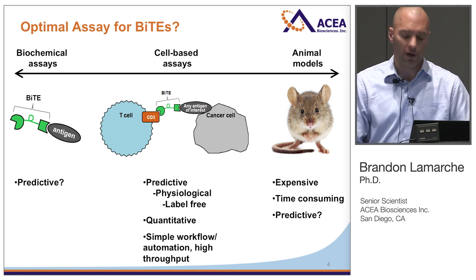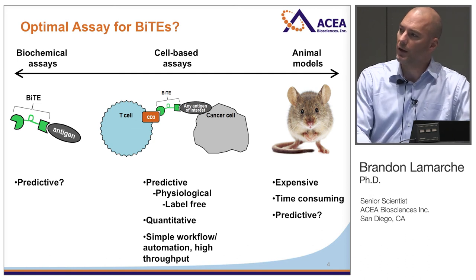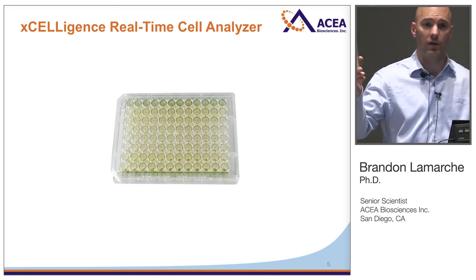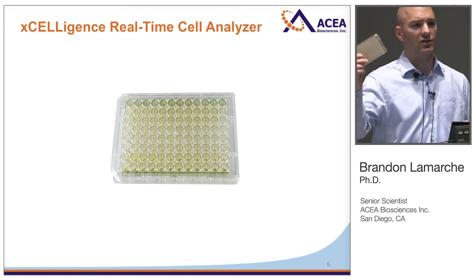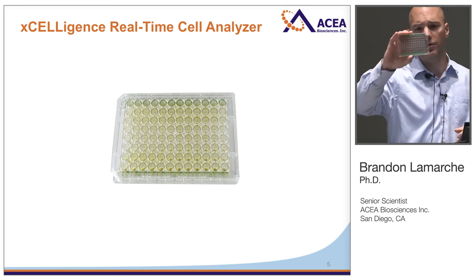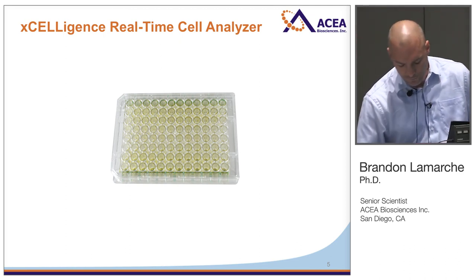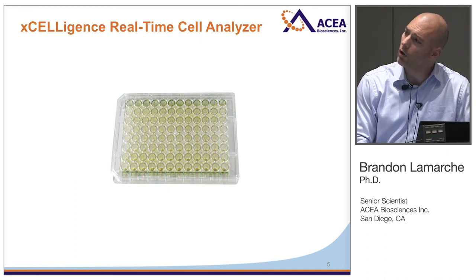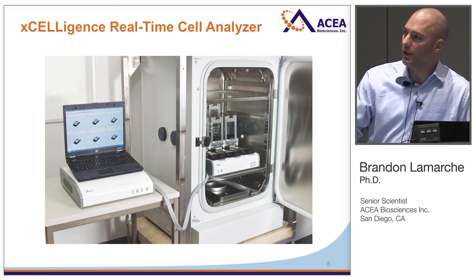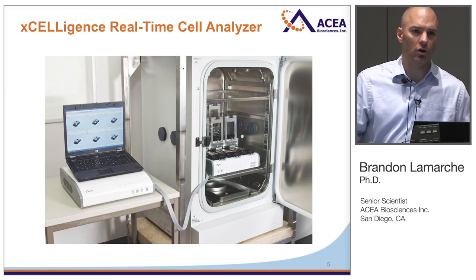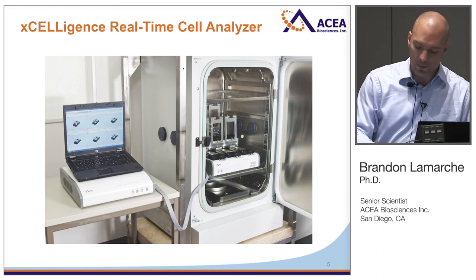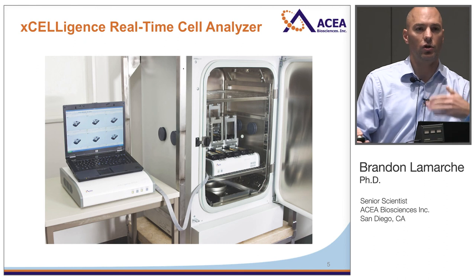You'd also like the workflow to be as simple as possible, automated, and high throughput. What I'm going to show you now is that a technology that ACEA makes, called the xCELLigence real-time cell analysis instrument, meets all these criteria. The best way to introduce this instrument is to start with the microtiter plates it uses — they have the same dimensions as any standard microtiter plate, but the difference is that there are electrodes integrated into the bottom of each well. The plates go into the instrument, which sits inside a standard tissue culture incubator so you can control temperature, humidity, and atmospheric composition.